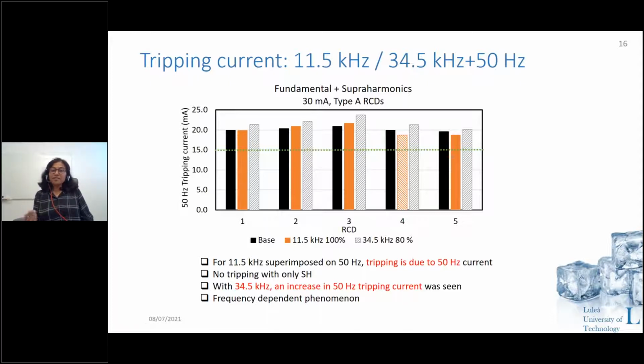And when we tested purely with supraharmonics, that is with no 50 hertz component, the RCDs did not trip, or if they tripped, it required really high currents, which is quite not possible to have in the leakage current. Then next is the 34.5 kilohertz component. It is a frequency dependent phenomenon, because in the case of 34.5 kilohertz, you require a higher fundamental component to trip the same RCD. So if you go higher in the frequency range, maybe the amount of 50 hertz component required increases. Here the concern is, as long as the 50 hertz component is below 30 milliampere, it is fine. But if the 50 hertz component increases above 30 milliampere so as to trip, then it will be a fail to trip scenario, and that is a dangerous situation.